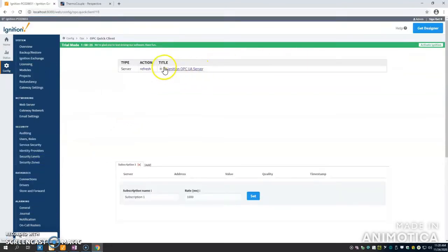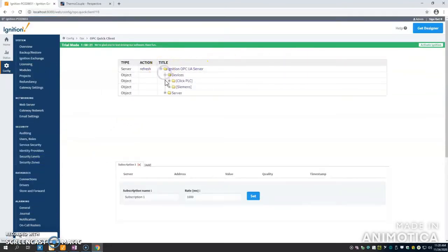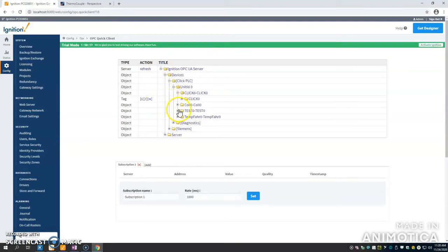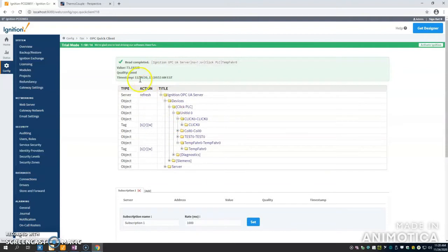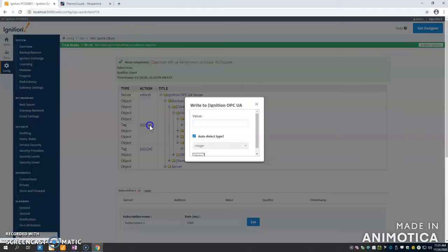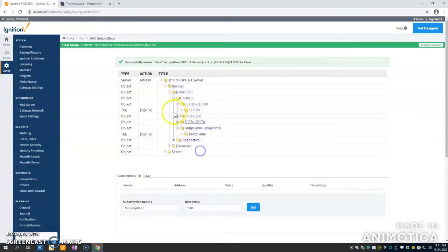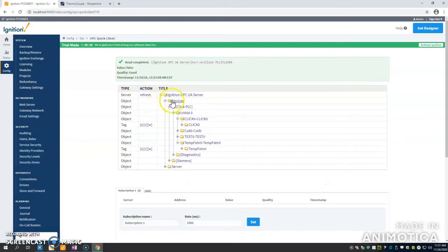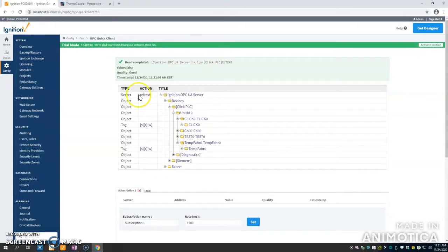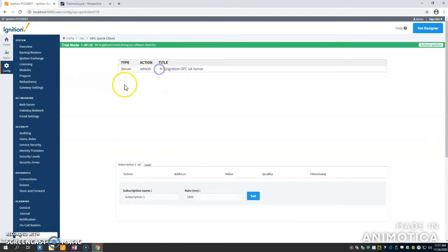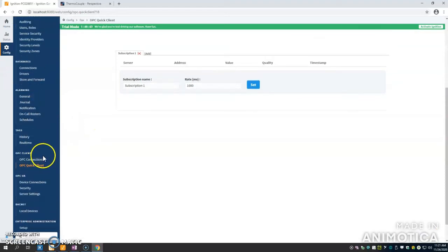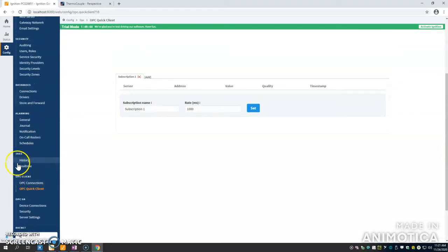And this is a quick client I was talking about. You can go down here, look at the devices, drill down to it, and then you have the different options where you can read and write or subscribe to it. So then you can read, it'll tell you if the quality's good, what the value is, you can write to it. For a floating point, I'm not going to write to it, but for a boolean, it's easy to write. You can pop it up, type in false. Depending on it, you can force it, it'll auto-detect it. It's a very smart software. You don't have to define it or anything. That's just super useful to troubleshoot. This is how you'll go through and make sure each tag is inputted correctly. Once again, in terms of a Siemens or an Allen Bradley, it wouldn't be as big of a problem, but a Click, it does have to be considered.